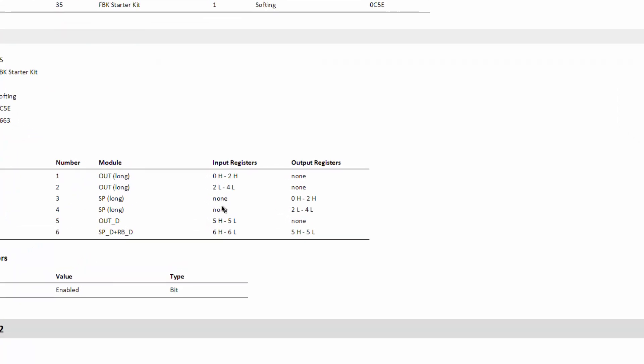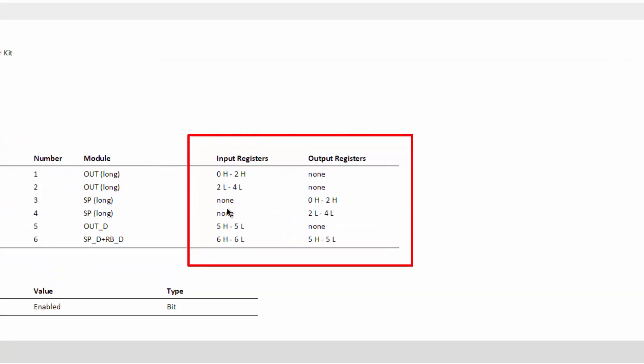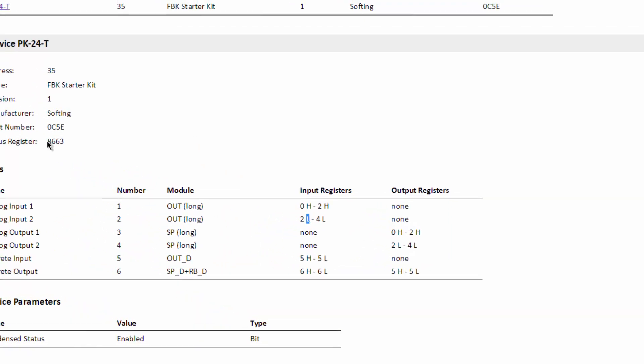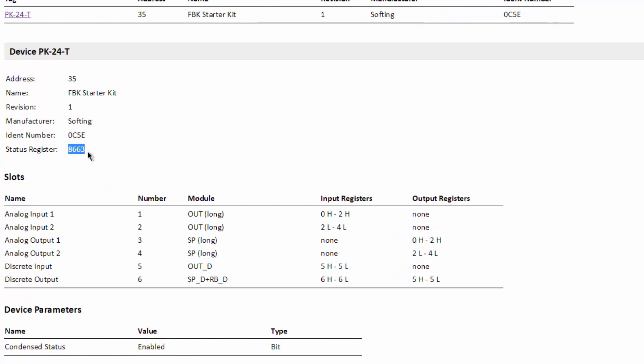Input data is mapped to input registers; output data is mapped to output registers. The data of the device is stored one by one on the registers. The data of a module can start or end on the high or low byte of a register — indicated by H for high and L for low. Also in the report, the register is displayed on which the status information of the device can be found.